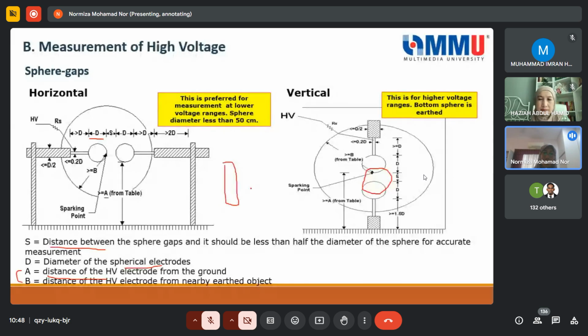For example, if I have the transformer breakdown or the withstand test, I'm not sure whether you cover the testing already in the syllabus, but for the withstand test, for example, for the transformer, maybe 75 kV for positive. But the withstand test for the negative will be higher. Maybe for negative, it would require 80 kV to give a breakdown. It means that the withstand test for the transformer gives 80 kV under negative, because negative, in general, gives a less severe impact compared to the positive polarity.